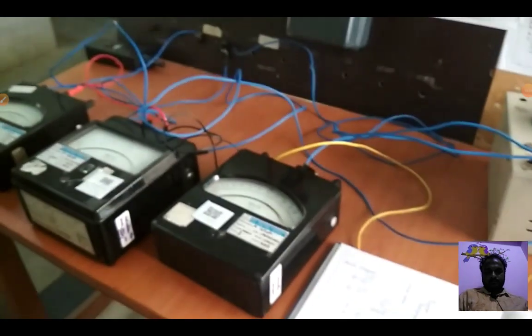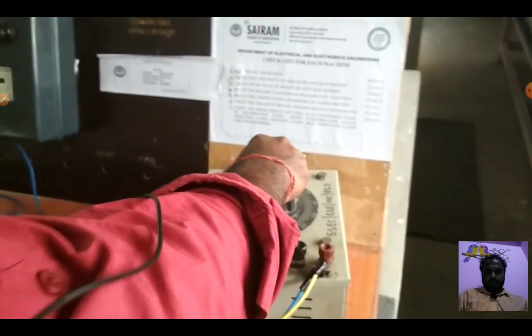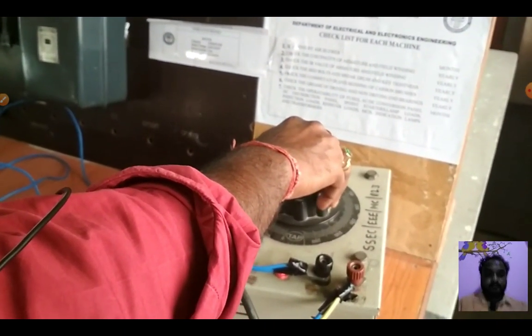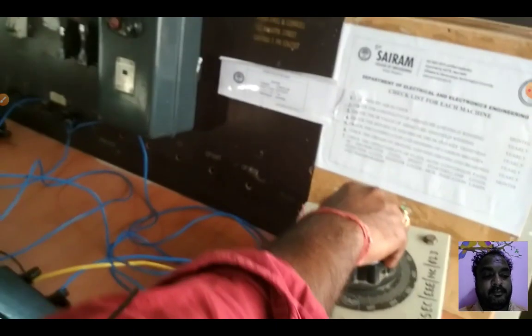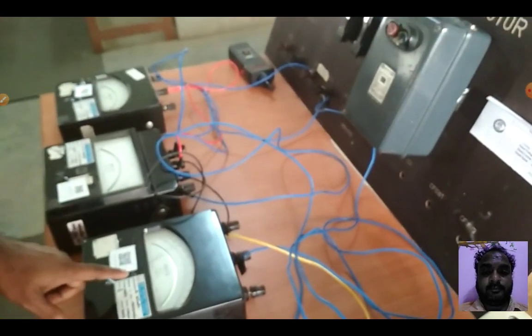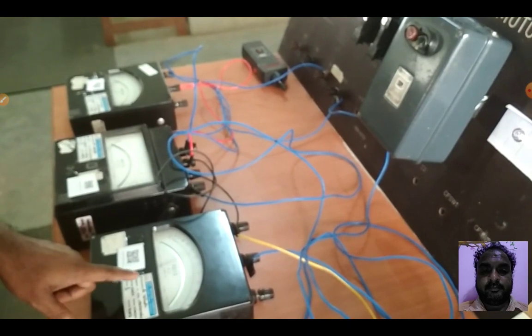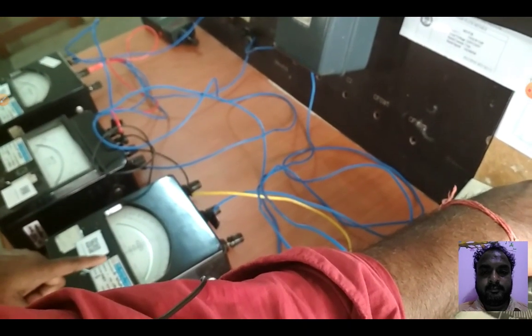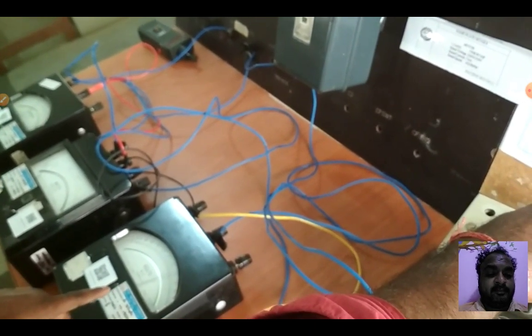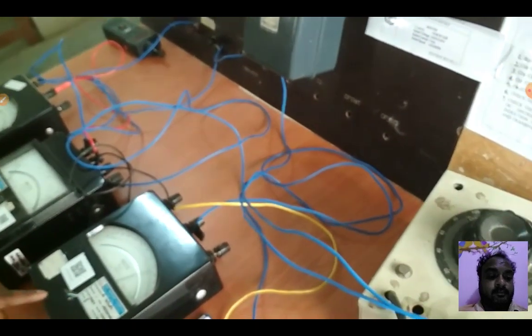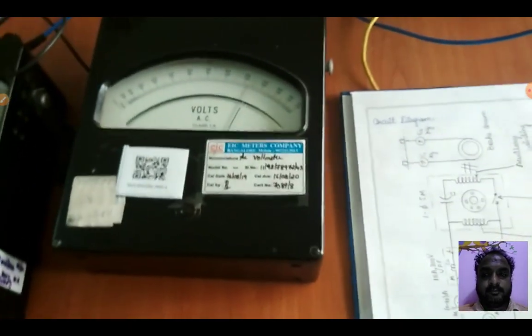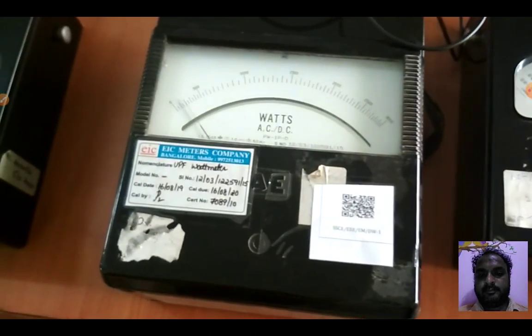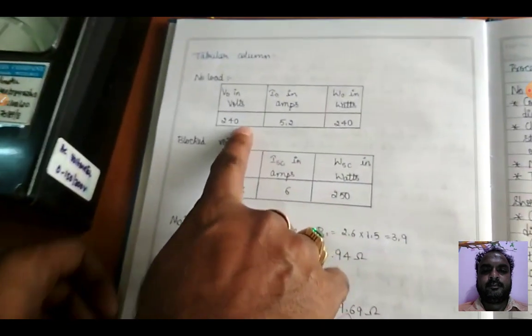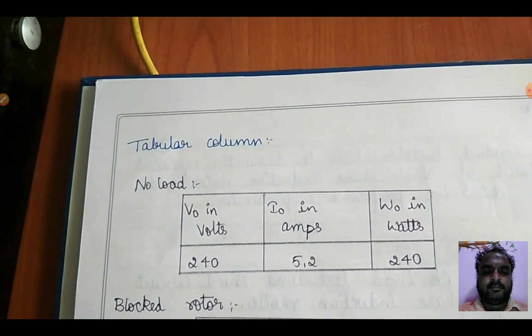The main supply. First we will conduct the no load test. So in no load test, set the rated voltage by using the single phase auto transformer. The rated voltage we can check in the voltmeter. So we need to set 230 volts in the voltmeter. Note down the current and wattmeter readings in tabular column. So these are our no load readings: voltage, current, wattmeter.